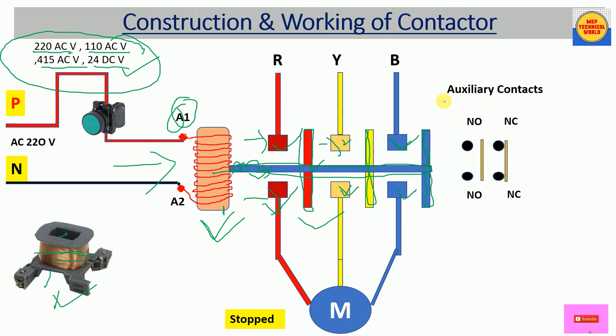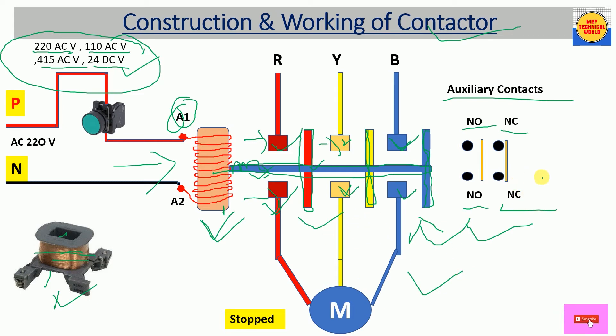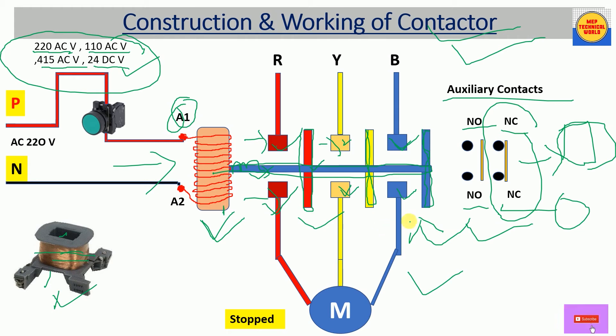We also have normally open contacts and normally closed contacts. These auxiliary contacts can be used for holding or latching purposes, or the remaining auxiliary contacts can be used for monitoring the contactor condition — whether it is off or on. You can connect indicators here to monitor the contactor. These are the major components of this contactor.